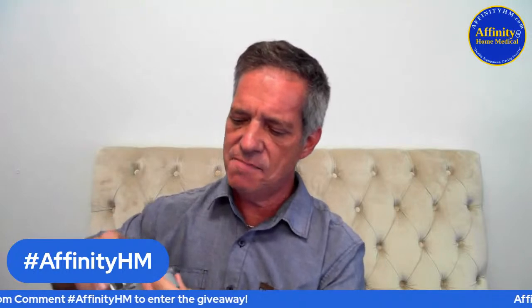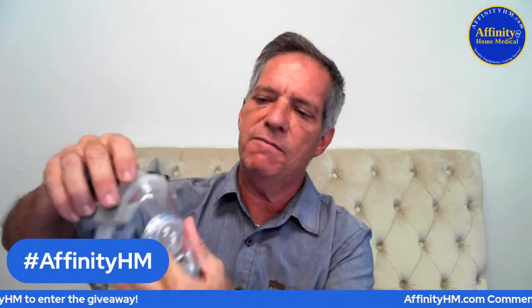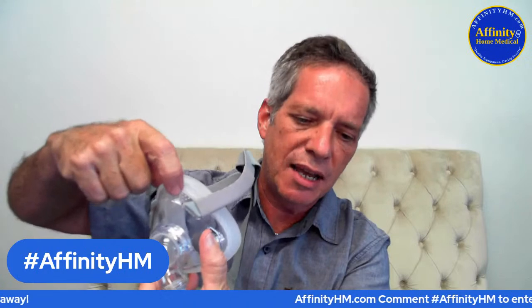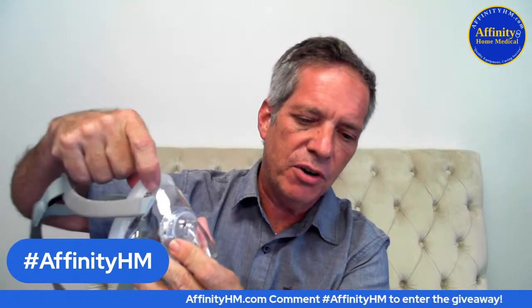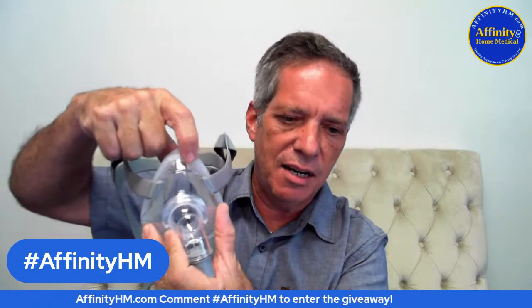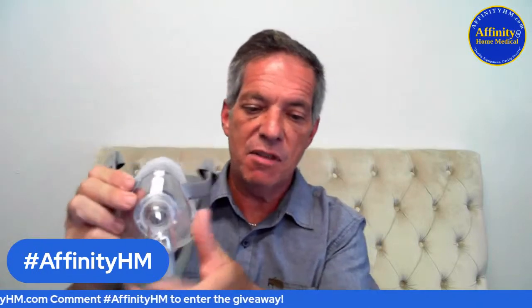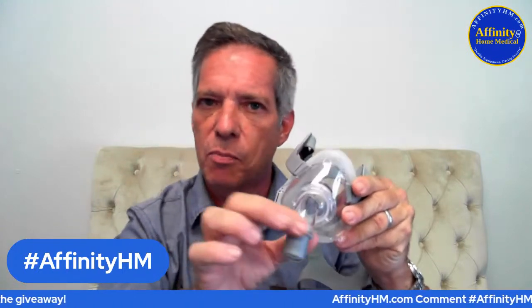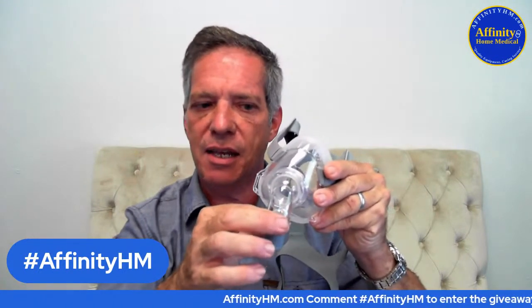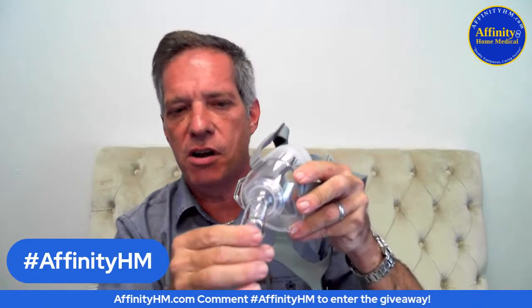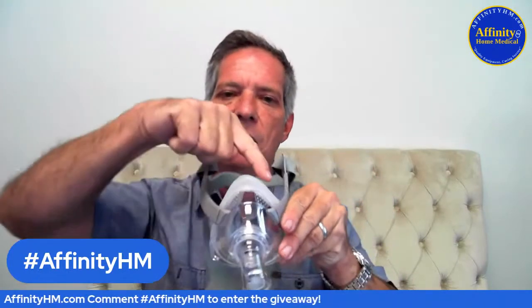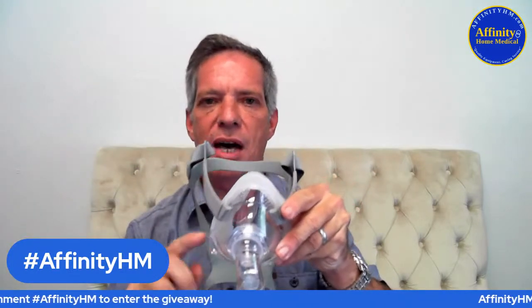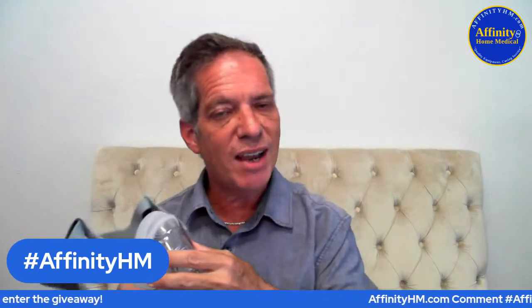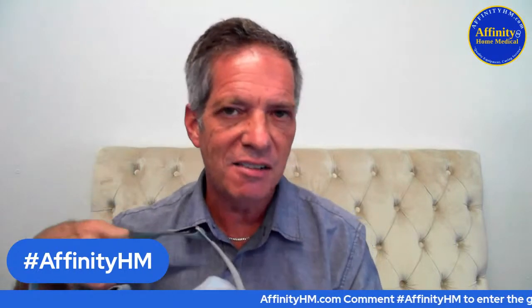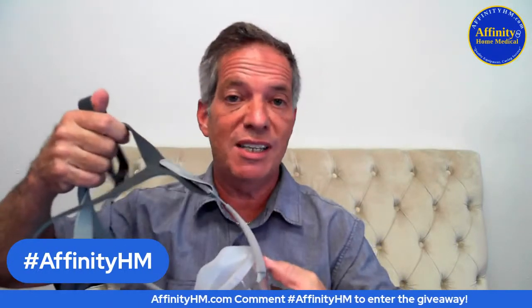All CPAP masks, again, will have some type of diffuse area with holes. This one has the holes here and here on each side so that the carbon dioxide can come out of the system. Many of the masks actually have a fitting right here that allows somewhat of a purposeful leak there so that carbon dioxide can get out. So if you're leaking here or here, no problem. But if you're leaking up here around the top or around the bottom, then either you do not have the correct amount of tension, it might not be tight enough, or it could just be a wrongly sized mask.